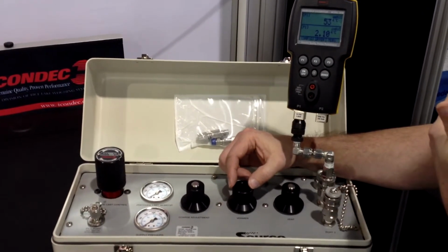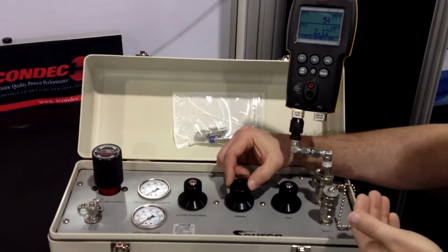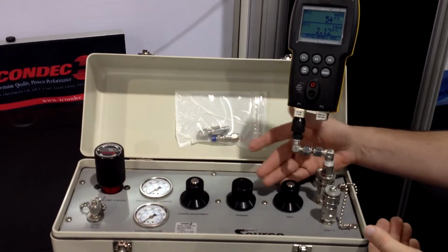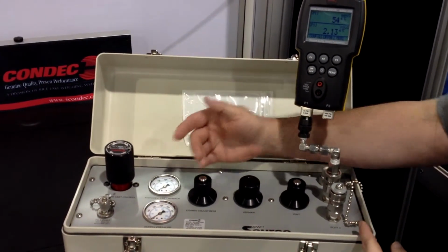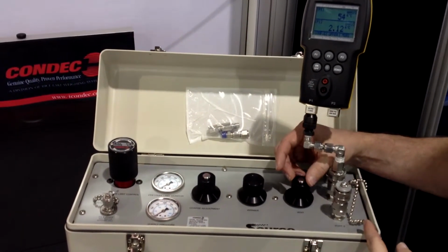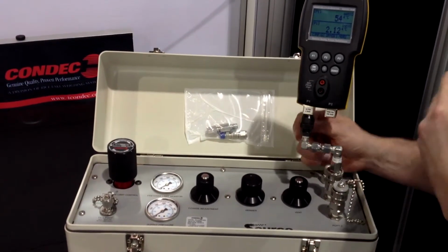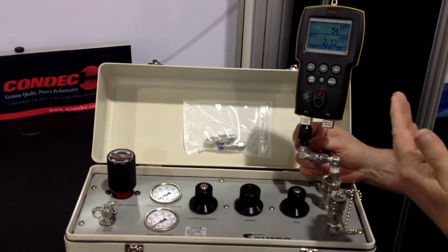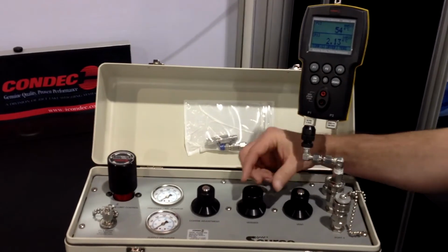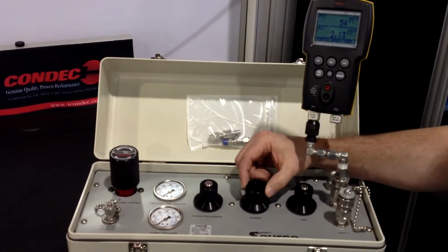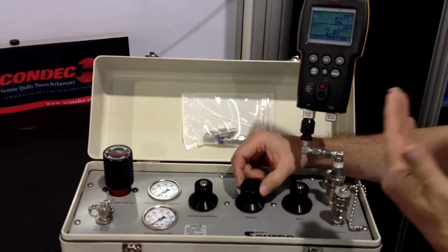Once you've gone to full scale and you want to come back down doing your hysteresis, you would reverse the process. Instead of using your coarse adjustment, you would use your vent valve and bleed off the nitrogen until you come a little bit above your target pressure. Lock down your valve, and then again dial in using your vernier to reach your target value coming back downward on the scale.